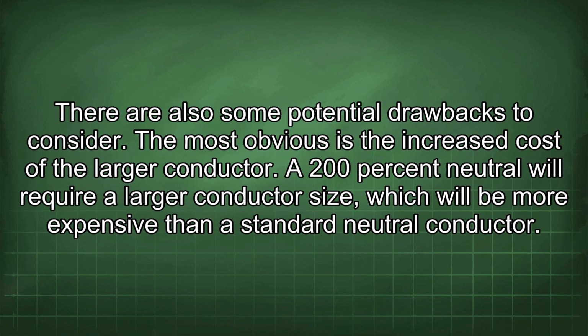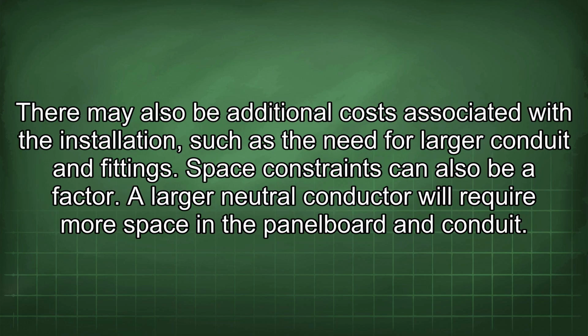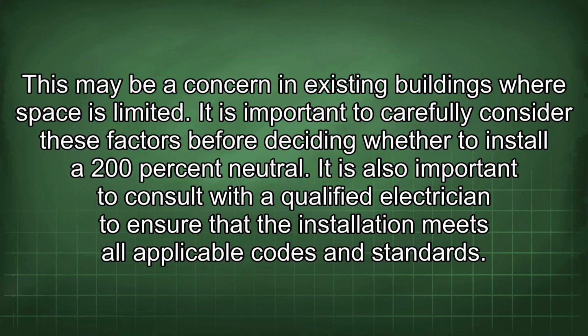The most obvious is the increased cost of the larger conductor. A 200% neutral will require a larger conductor size, which will be more expensive than a standard neutral conductor. There may also be additional costs associated with the installation, such as the need for larger conduit and fittings. Space constraints can also be a factor. A larger neutral conductor will require more space in the panel board and conduit. This may be a concern in existing buildings where space is limited. It is important to carefully consider these factors before deciding whether to install a 200% neutral.